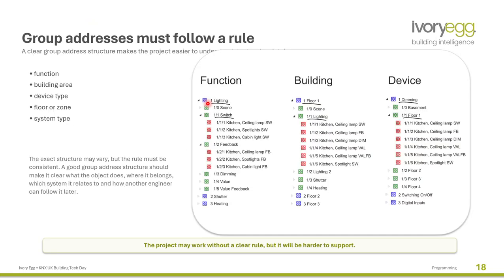For the programming part, group addresses must follow rules. Your company should have its own rules, and you should try not to change them. For example, KNX books suggest a structure with the main group address for zone and floor, the middle group for function, and the sub group for sub-functions. But you can do whatever you like, as long as you follow the rules you set from the first time.